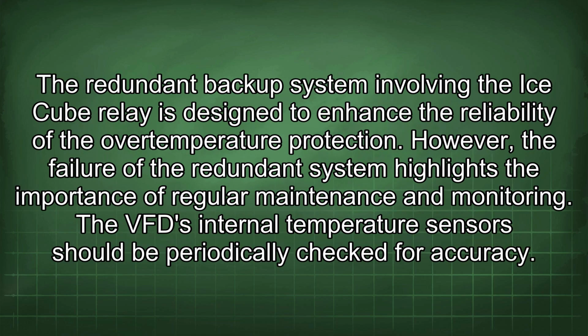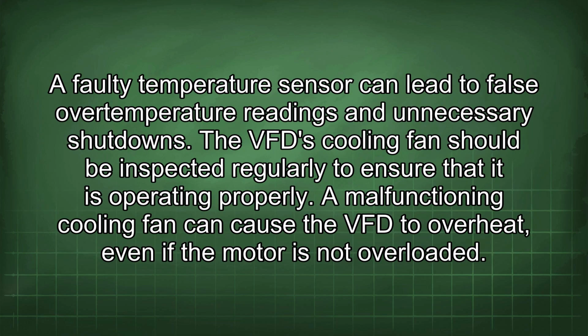The redundant backup system involving the ice cube relay is designed to enhance the reliability of the overtemperature protection. However, the failure of the redundant system highlights the importance of regular maintenance and monitoring. The VFD internal temperature sensors should be periodically checked for accuracy. A faulty temperature sensor can lead to false overtemperature readings and unnecessary shutdowns. The VFD cooling fan should be inspected regularly to ensure that it is operating properly. A malfunctioning cooling fan can cause the VFD to overheat, even if the motor is not overloaded.